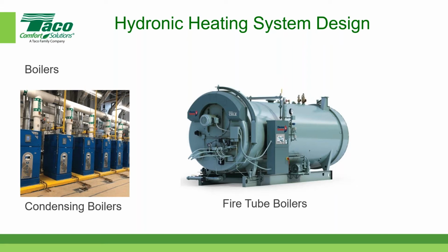But the two major categories are condensing boilers, which is on the left, and non-condensing boilers. And the one on the right is a fire tube boiler. Fire tube boilers have been around for a very, very long period of time. And for the longest time, they were sort of the workhorse for large commercial projects. I know that going back probably about 40 years ago, nearly all of our projects that were of any reasonable size used fire tube boilers.